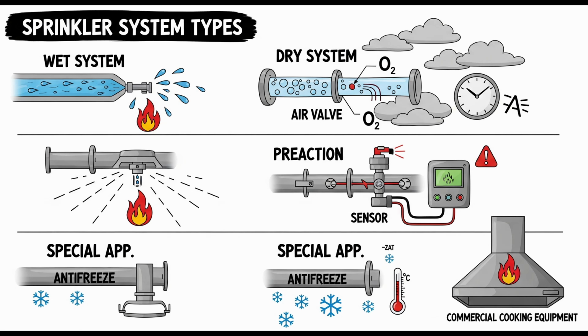What about hydrostatic testing these antifreeze systems? If pendant sprinklers are used in an antifreeze system, sprinklers hanging down, then all the plain water used for the initial hydrostatic pressure testing must be drained completely from the entire system after testing is finished. That is, unless the hydrostatic testing was performed using a listed antifreeze solution instead of water in the first place. Why is draining the plain water so critical, especially with pendant heads? It seems obvious you'd drain it.